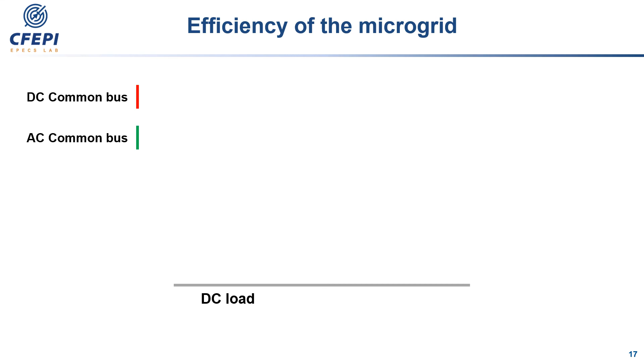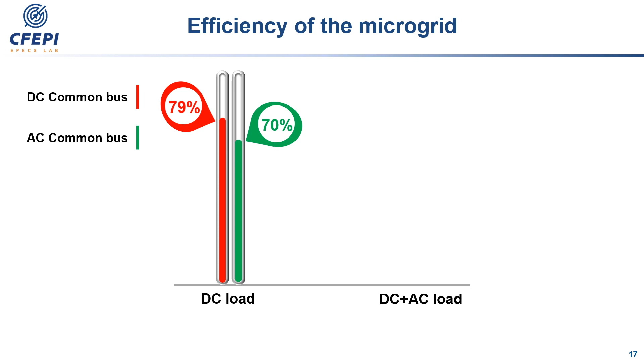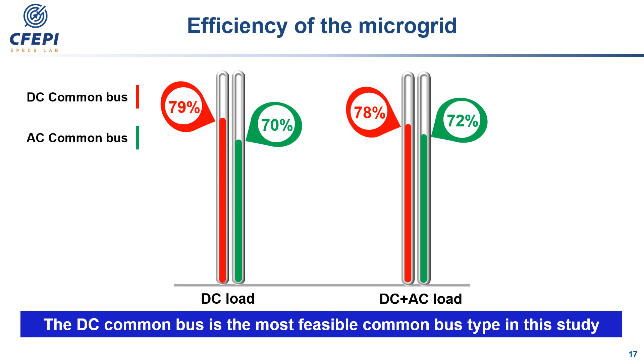For DC load, DC common bus efficiency is 79%, whereas for AC common bus it is around 70%. For both types of loads, the DC common bus efficiency is around 78%, whereas for AC common bus it is 72%. As can be seen in this figure, the DC common bus has higher efficiency during all the scenarios. Therefore, DC common bus is the most feasible common bus type in this study. Moreover, DC common bus is more advantageous in case of DC loads only.